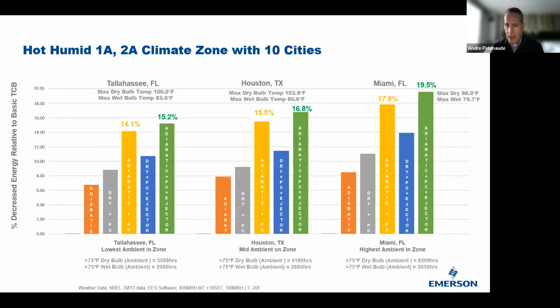If you just had adiabatic alone in Miami, you would be saving a little over 8% over a standard transcritical booster system. And you go to the gray line, if you just had a dry gas cooler with parallel compression, you'd be somewhere at about an 11% savings over a basic transcritical booster. But if you add both, you're at 17.8% with adiabatic plus parallel compression. And this is where designers and end users have to decide, okay, what's really important to my decision making, and that's what Derek's going to drill down into.